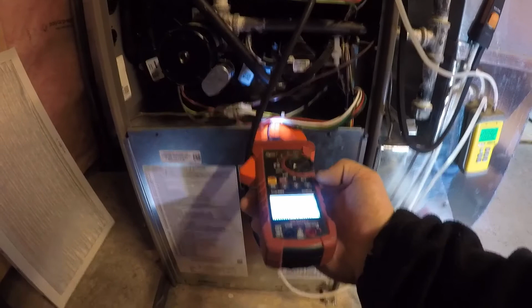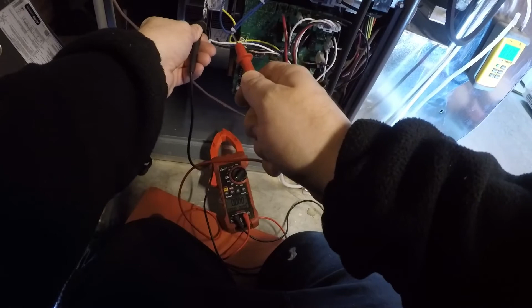I don't know if you guys can see that there. Typically, it should be lower on these. I think my static's affecting that. So another reason to correct static pressure is to reduce energy costs. So, once I'm done that, I hook up my leads and take my voltage readings. So we have incoming voltage, 119. We'll capture that.